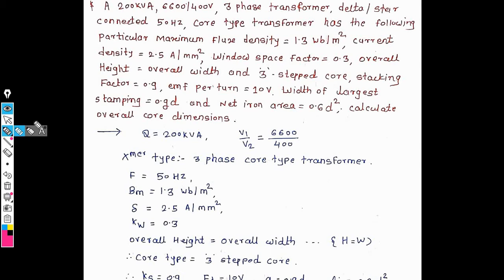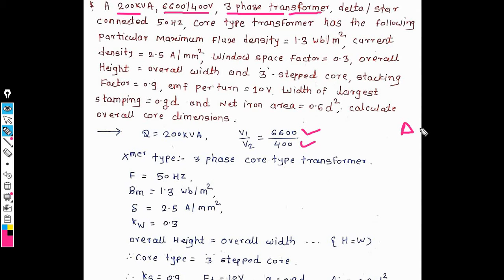This problem is based on a three-phase transformer. A 200 kVA step-down transformer with voltage rating V1 (input) and V2 (output), using delta-star winding — primary winding is delta and secondary winding is star — connected at 50 Hz. It is a core-type transformer with maximum flux density Bm = 1.3 Weber per meter square and current density sigma = 2.5 Ampere per mm square. Window space factor Kw = 0.3.